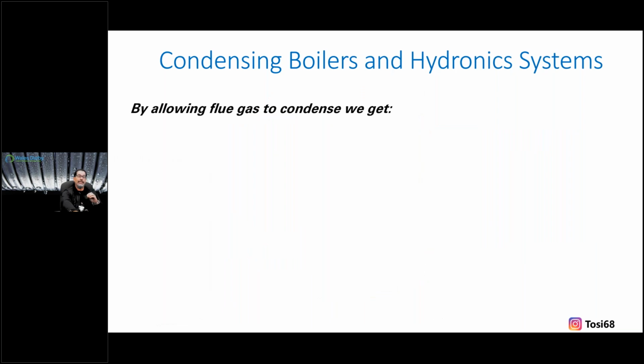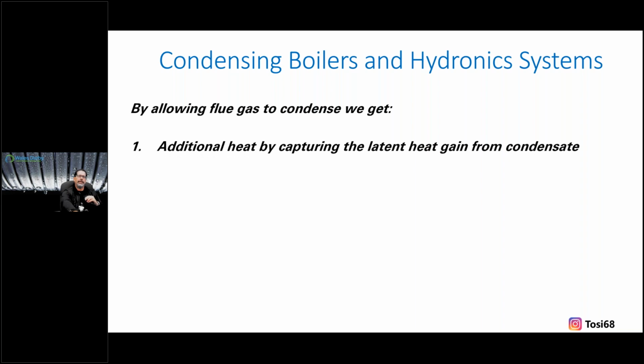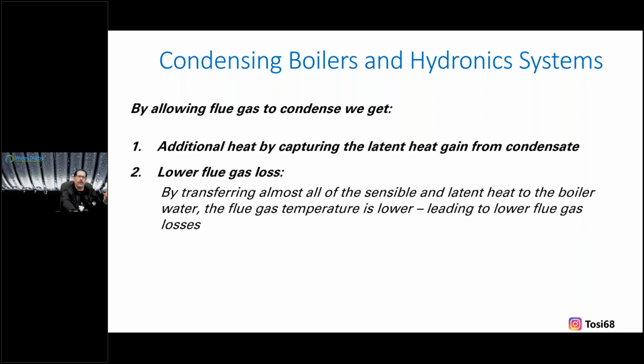So by allowing the flue gas to condense, right, we get some benefits here. Additional heat by capturing the latent heat that's normally just leaving up the flue or out our venting, right? Lower flue gas loss, transferring almost all the sensible and latent heat to the boiler's water. We are now in that better state of efficiency, the higher efficiency as it's labeled. Don't get tricked by a yellow tag saying 96% AFUE or something like that, because in theory, that's what it was rated for. It doesn't mean we're achieving that just because we hung it on the wall, all right? The flue gas temperature is lower, leading to lower flue gas losses, right? So we're not losing anything outside. We're keeping it in the envelope, again, BTUs to match, and now we're condensing, achieving high efficiency, right?